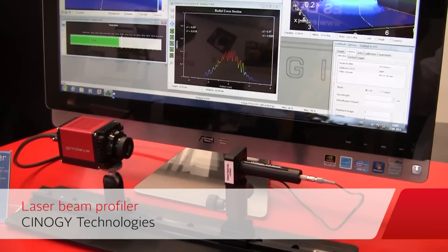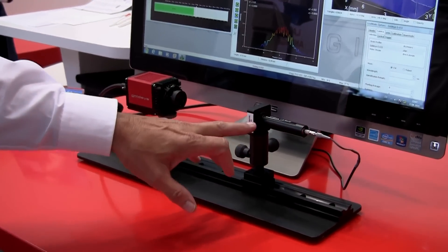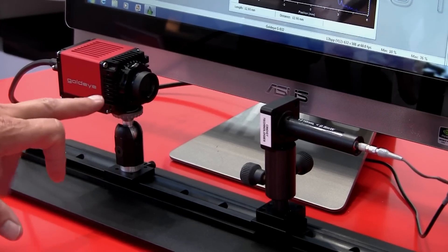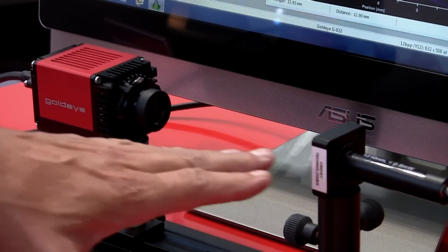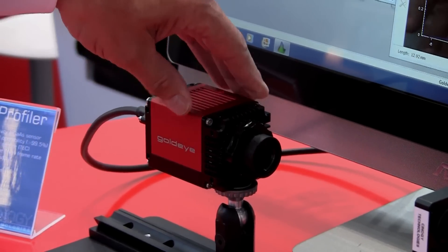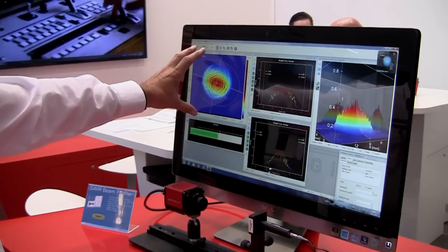Here we see an application for the shortwave infrared cameras — laser beam profiling. This application is used to measure lasers and guarantee their quality over time, so you have to measure them periodically. This laser operates at a wavelength of 1310 nanometers, so it is not visible to the naked eye. The laser goes directly to the shortwave infrared camera and is measured there. The software, written by the company Cinogy, shows you the profile of this beam.